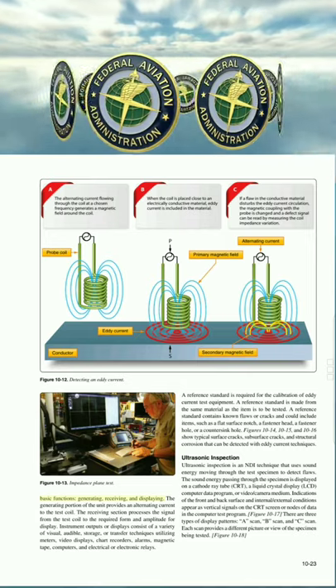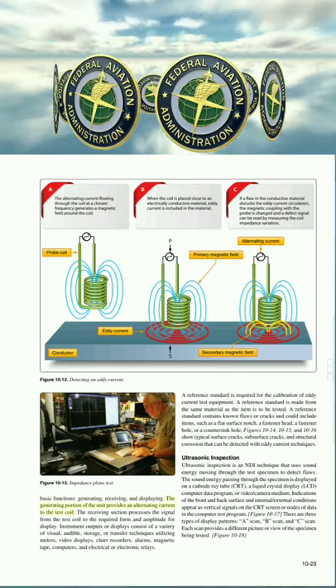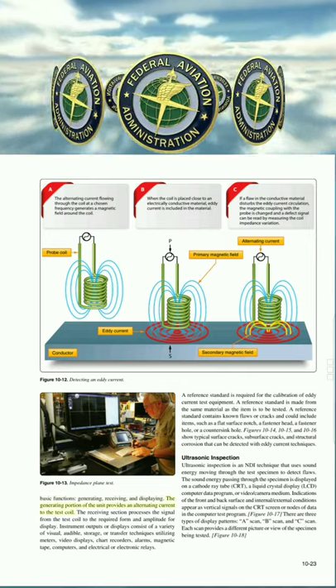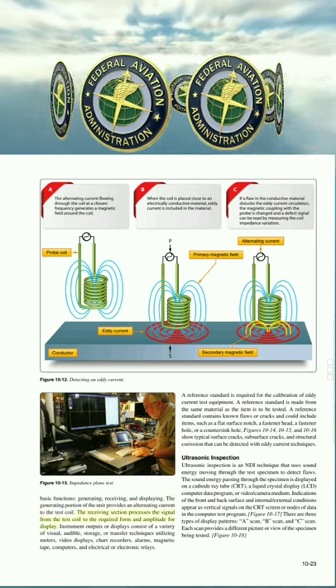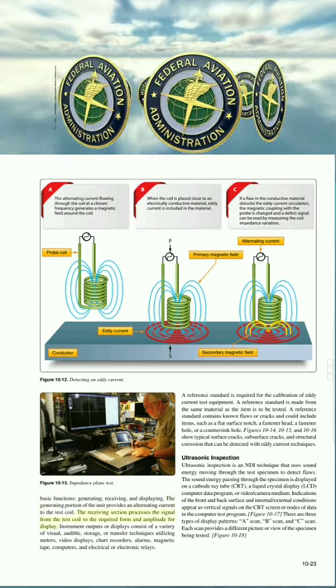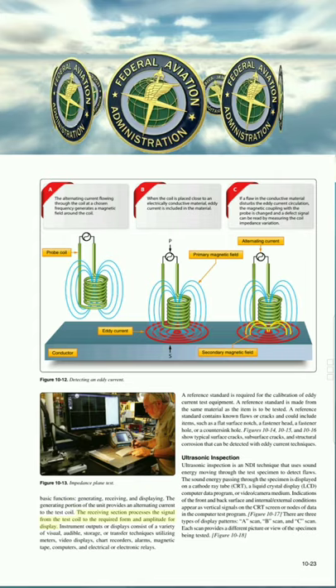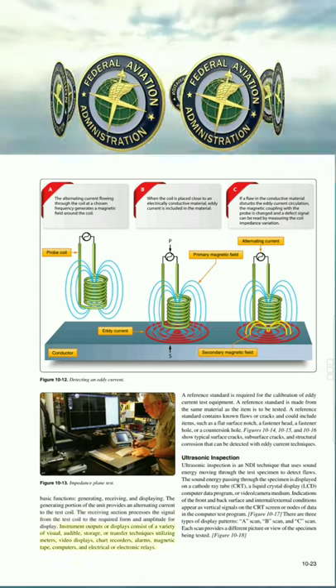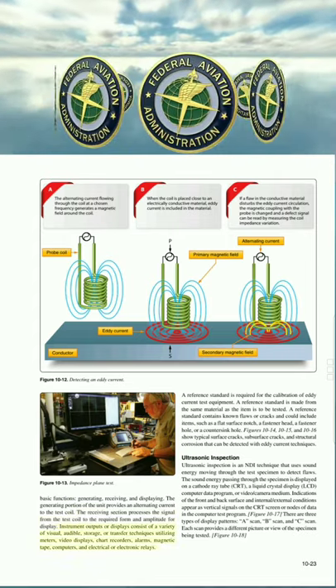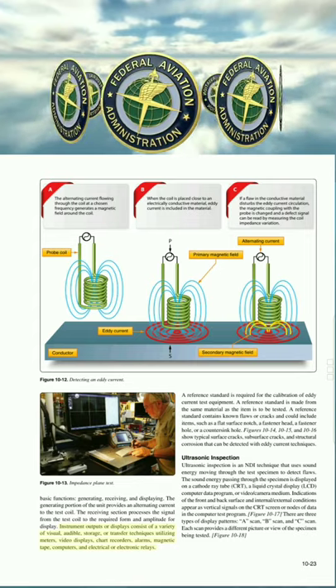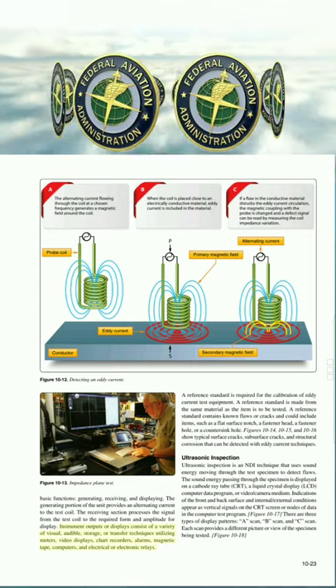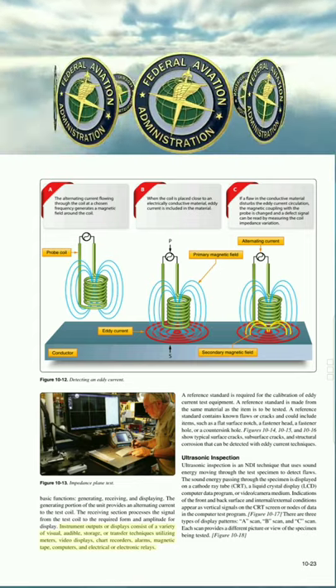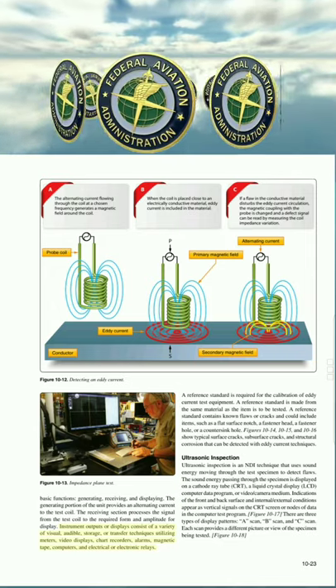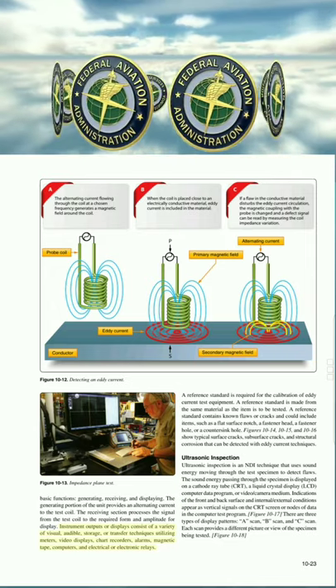Generating, receiving, and displaying. The generating portion of the unit provides an alternating current to the test coil. The receiving section processes the signal from the test coil to the required form and amplitude for display. Instrument outputs or displays consist of a variety of visual, audible, storage, or transfer techniques utilizing meters, video displays, chart recorders, alarms, magnetic tape, computers, and electrical or electronic relays.